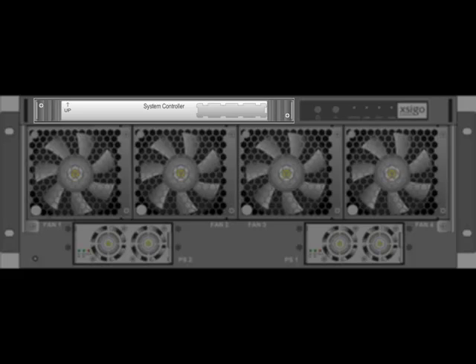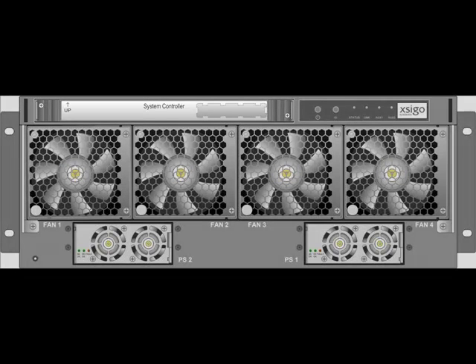The SCP is a system on a board with a processor, memory, a hard disk, compact flash storage, and all the management interfaces we will use to communicate with the chassis. The SCP is hot swappable, but the chassis will require a reboot after the SCP is swapped out.